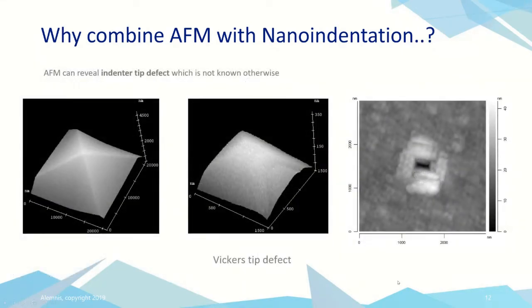Okay, finally on that note, the AFM can also be used to image the indenter. So we can see what the indenter apex actually looks like. And we can also image very shallow indents to understand if we have a tip defect. Now, with three-sided pyramids, the tip defect is not as pronounced, but with four-sided pyramids, such as the Vickers shape, at very low loads, it's almost impossible to have a perfect apex, and we usually have a flat in one direction, which you can see very clearly here in this AFM image.